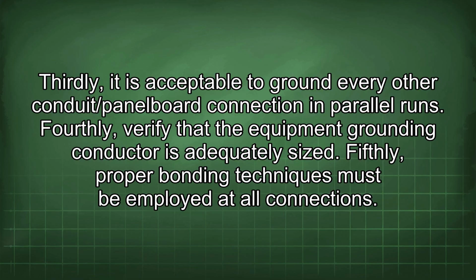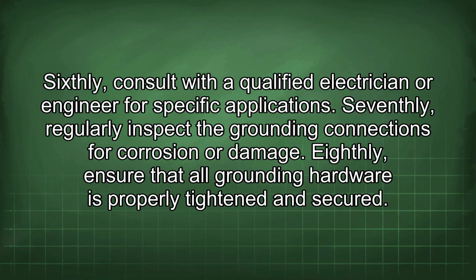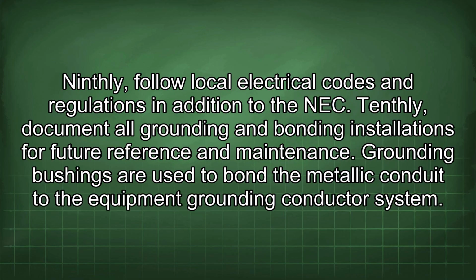Fourthly, verify that the equipment grounding conductor is adequately sized. Fifthly, proper bonding techniques must be employed at all connections. Sixthly, consult with a qualified electrician or engineer for specific applications. Seventhly, regularly inspect the grounding connections for corrosion or damage. Eighthly, ensure that all grounding hardware is properly tightened and secured. Ninthly, follow local electrical codes and regulations in addition to the NEC. Tenthly, document all grounding and bonding installations for future reference and maintenance.